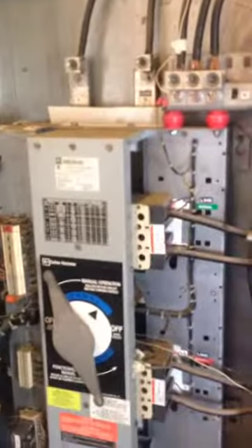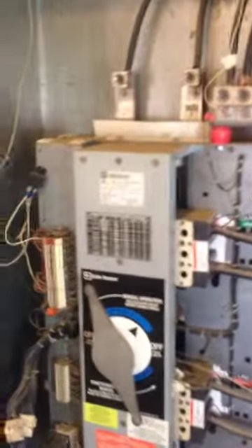So, the fact that we keep getting something that's shutting down the inverters and now that backfeed error, to me, tells me that the transfer switch, something with that, is a problem. I did have a guy who was a representative for a generator company and knew quite a bit about electric. He came through all here and he put a voltmeter and looked on all the different things while the system was running, and he couldn't find anything that was out of the ordinary.